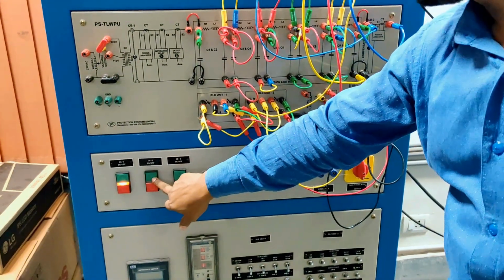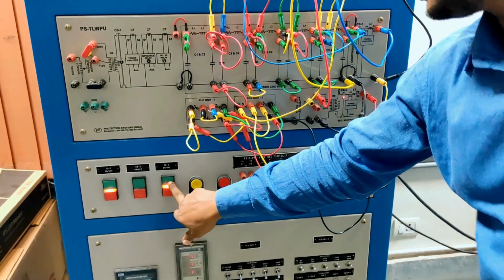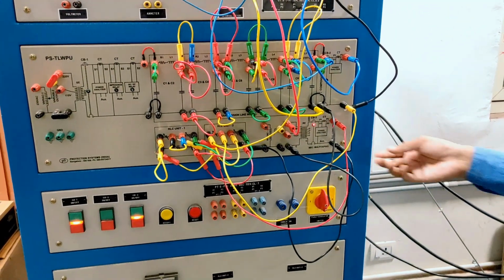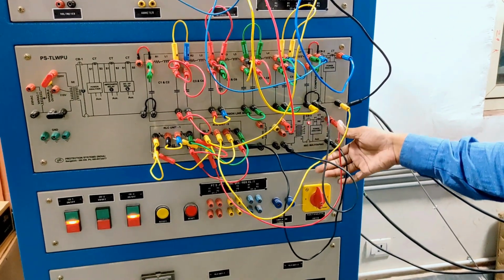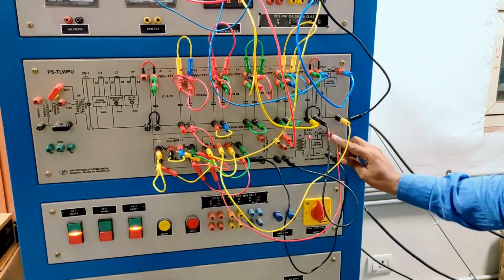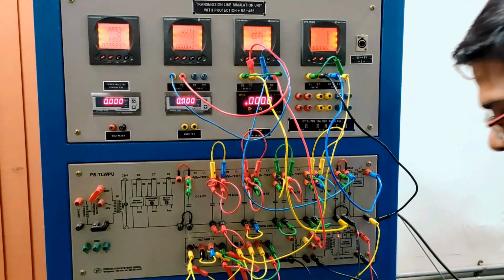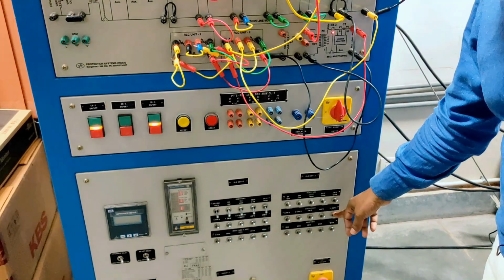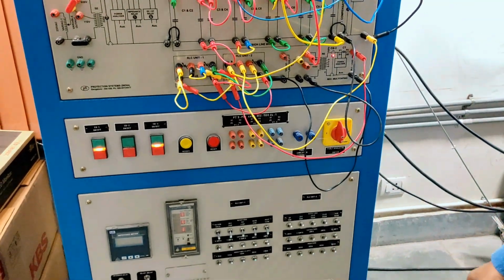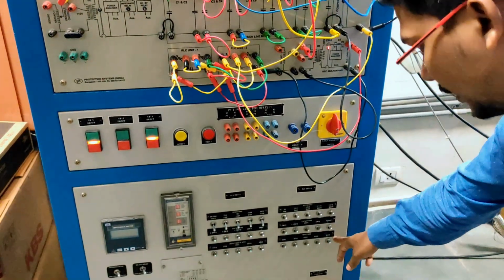So now we have to make zero voltage regulation at no load. What we will do is turn on circuit breaker 3. If we turn on circuit breaker 3, the compensator or RLC unit will be connected across the tap changing transformer, and we can turn on the corresponding element. Because we have to reduce the voltage, we have to turn on the inductor.